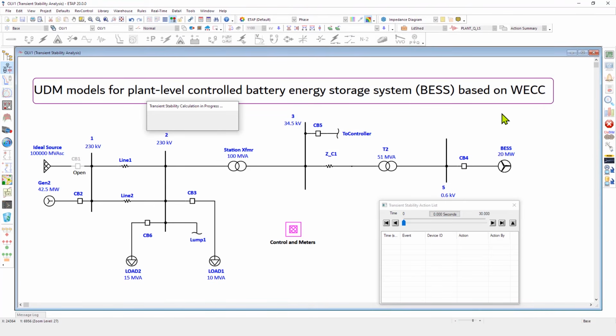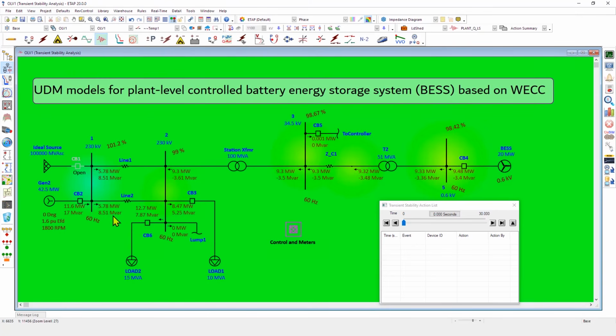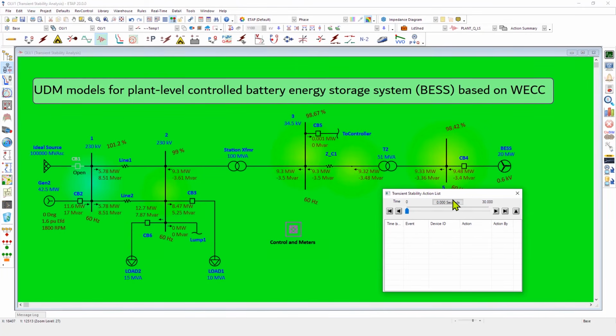So combining the transfer functions from UDM and the dynamics from various elements, we can run a network simulation in transient stability and solve the power flow at different steps in time. Just like with time domain load flow and E-tracks, transient stability also provides us with an action slider as well as a time slider that allows us to move the simulation as a function of time and observe various user-defined actions as well as the program-related actions or automated actions such as relay trips in this event list.